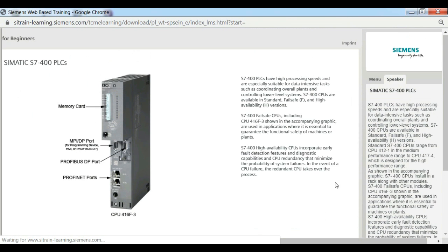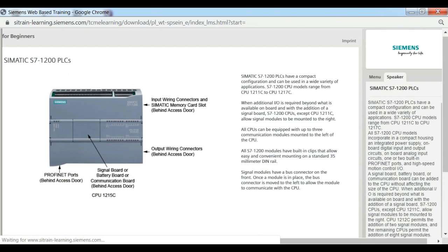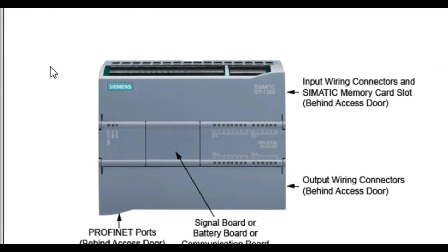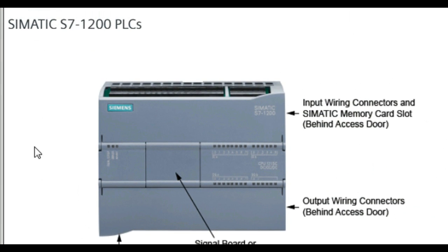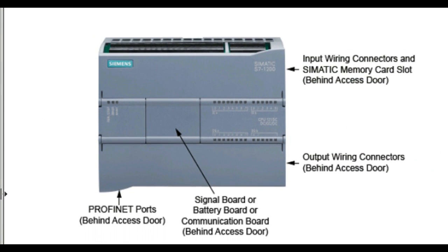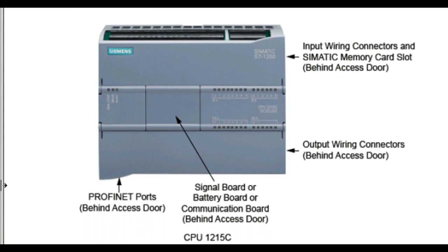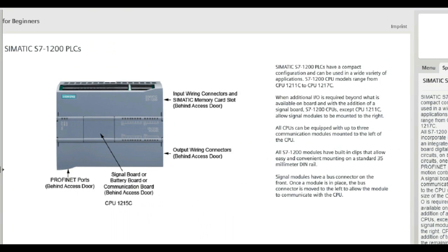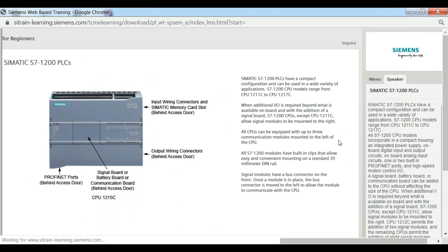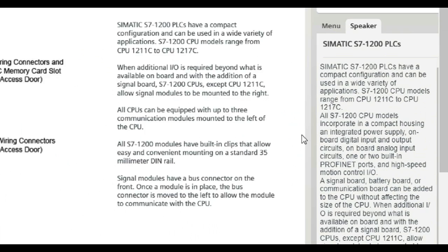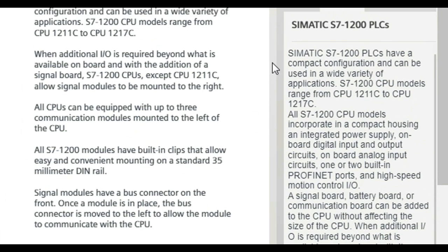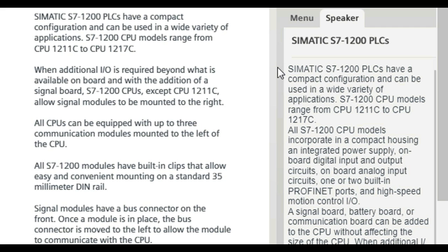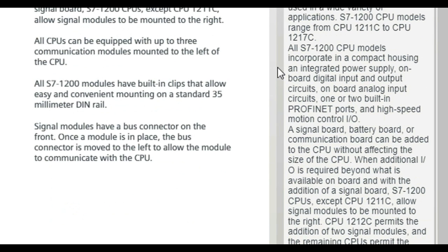SIMATIC S7-1200 PLCs have a compact configuration and can be used in a wide variety of applications. S7-1200 CPU models range from CPU 1211-C to CPU 1217-C. All S7-1200 CPU models incorporate in a compact housing an integrated power supply, onboard digital input and output circuits, onboard analog input circuits, one or two built-in PROFINET ports, and high-speed motion control I.O.